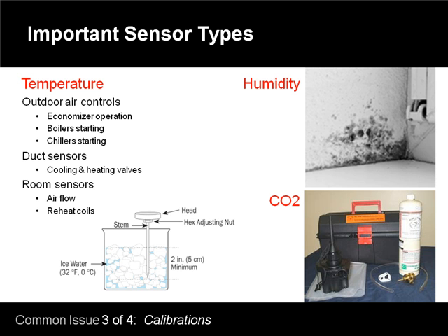can. Sensors and calibrations are very complicated, almost magical, kind of. So first I'd like to describe the different types of sensors that we have out there. The first one is temperature controls. Everybody's pretty familiar with them, because that's what controls the temperature in your space, like the thermostat you have on the wall. Economizer operation or air controls: you get free cooling when the outside air drops low enough that you can bring in outside air and cut your chillers off or give them a little bit of a rest. You also have boilers that start up when the outside air temperature drops and you need to get heating in the building.